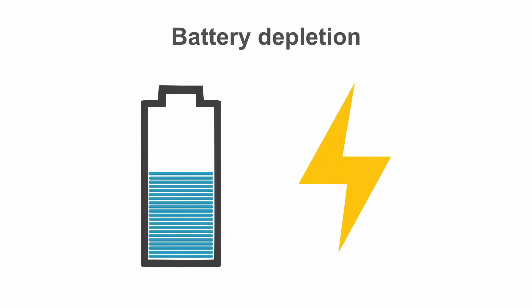Another consideration is battery depletion. If we think about the battery pouring loads of its energy into the capacitor for every shock, this can really deplete the energy. Estimates suggest that for every shock delivered by the device, this can reduce battery longevity by one month. And if you think that some people can have up to 12 or even more shocks during an event, this can have huge implications on how long the device is going to last.